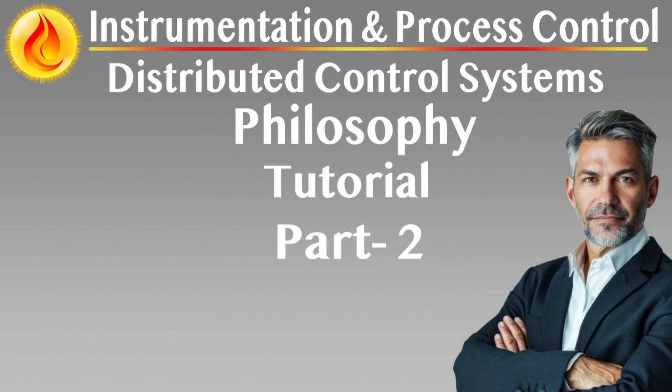Fail-safe logic philosophy. All safety logic is inherently fail-safe. Any loss of power, communication failure, signal open circuit, or diagnostic fault defaults to a safe plant condition, typically shutdown or isolation. De-energized to trip, DTT, principle applies to all final elements.